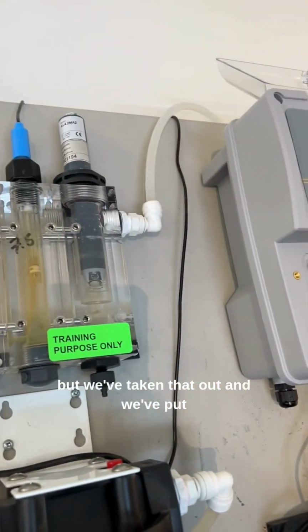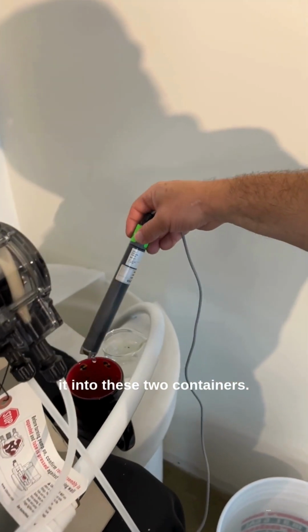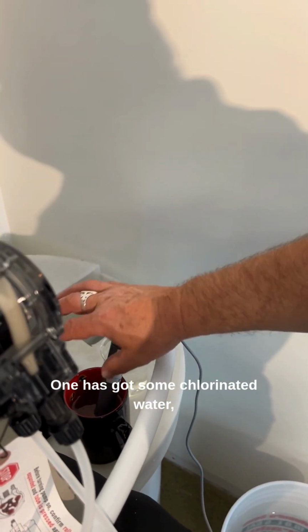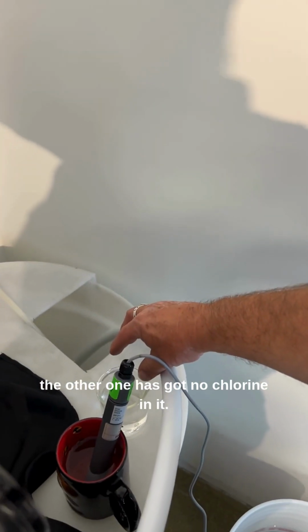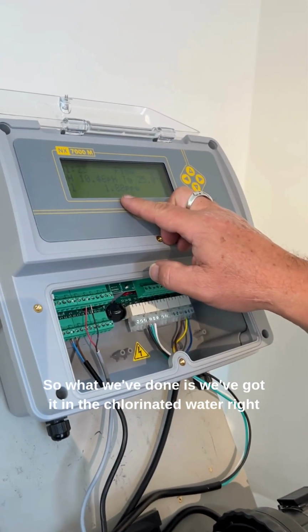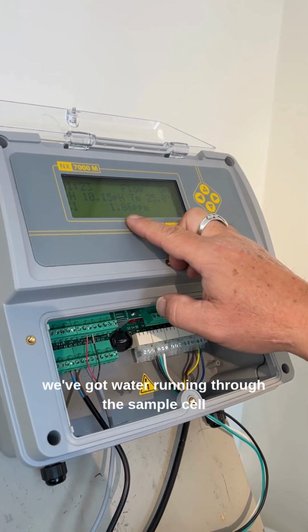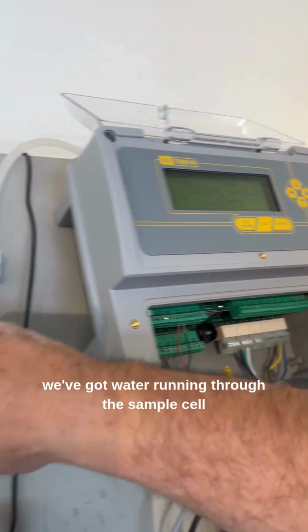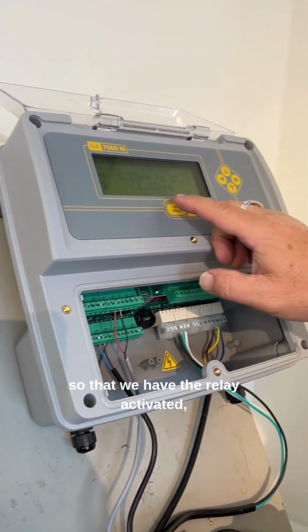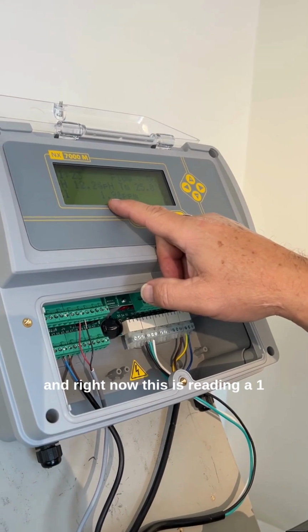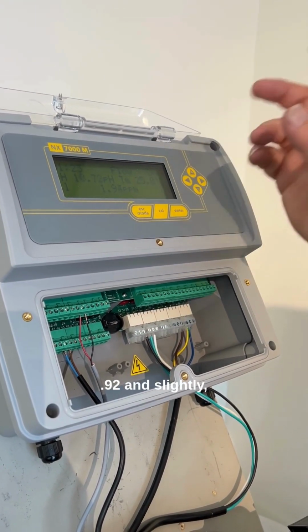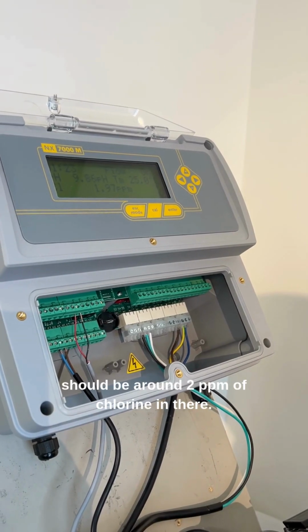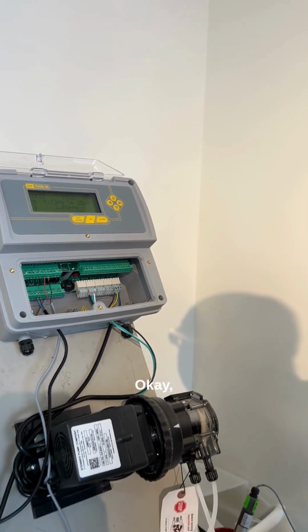But we've taken that out and we put it into these two containers. One has got some chlorinated water, the other one has got no chlorine in it. So what we've done is we've got it in the chlorinated water right now. We've got water running through the sample cell so that we have the relay activated. Now right now this is reading 1.92 and slightly climbing. Should be around 2 ppm of chlorine in there.